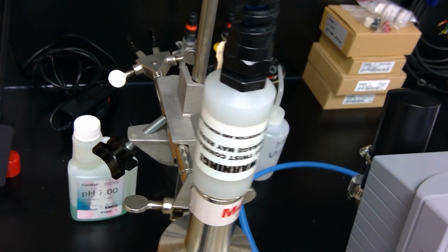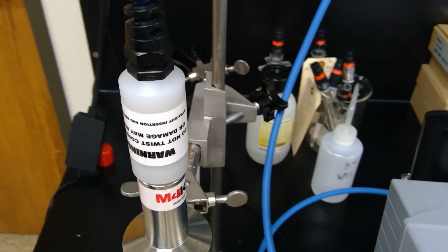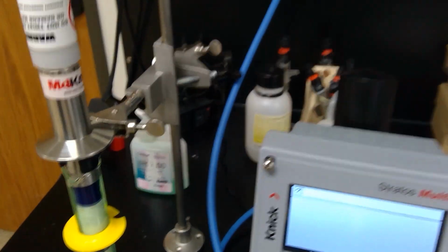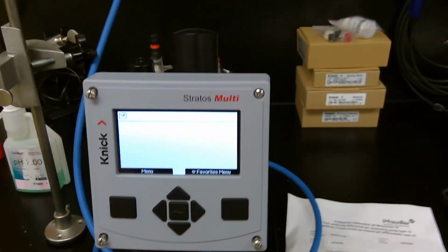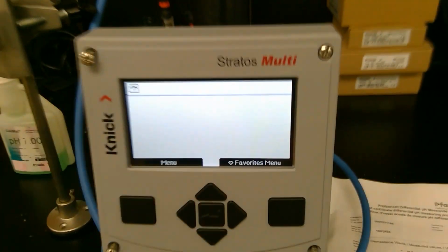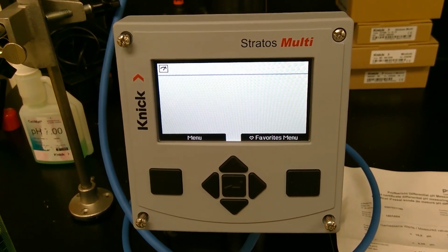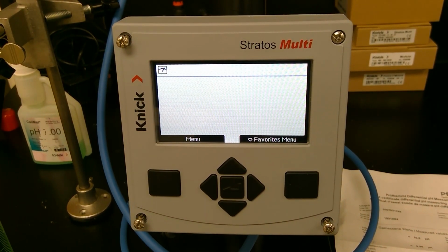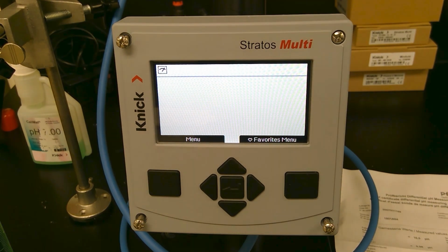Now, for those of you who can read upside down, it says do not twist connection. You want to do everything possible to prevent twisting that part that I slid down over the sensor. The reason is you can damage that connection, so just slide it off like I showed you. Connect the connector into the top of the Type 18, hear the snap, then slide that white portion back over top of it without turning it. So now we'll go ahead and move on to the configuration.